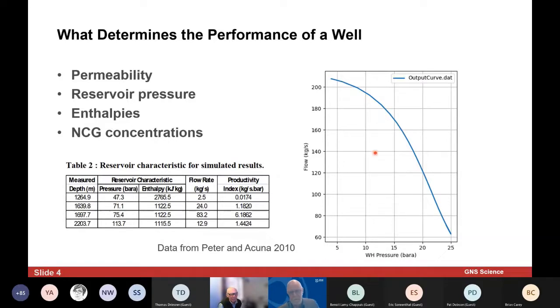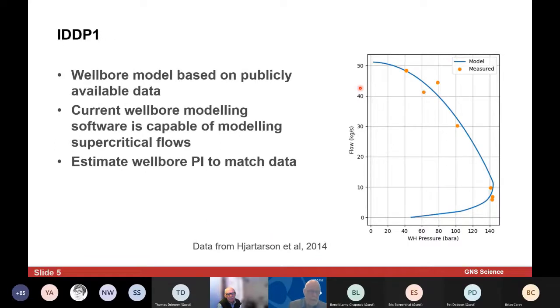What I'll sometimes be looking at here in terms of trying to understand the performance of a well is one of these things called an output curve. What we're looking at here is for that example from the Indonesian well that I showed before. We've got wellhead pressure along the bottom here and then we've got flow rate along the vertical axis. Typically a geothermal power station will run with wellhead pressures in the sort of 15 to maybe 8 bar range, although it is quite dependent on the setup.